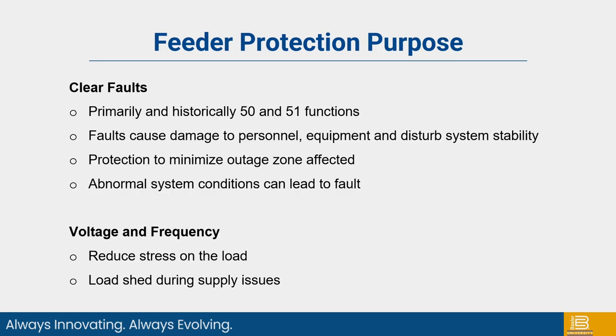So feeder protection purpose is primarily and historically 50 and 51 functions, so instantaneous and time overcurrent. Faults cause damage to personnel, equipment, and disturb the system's stability. So feeder protection is designed to minimize the outage zone affected and keep as much of the system in service as possible.